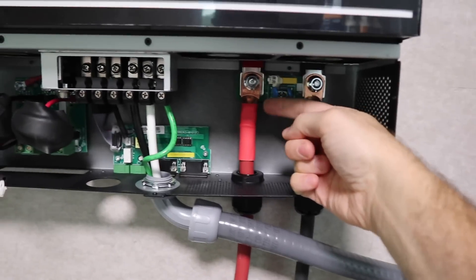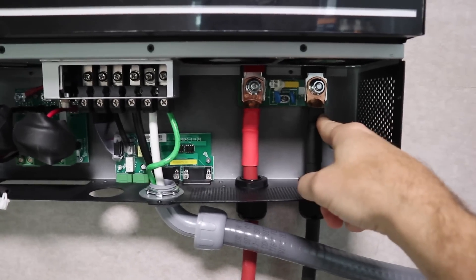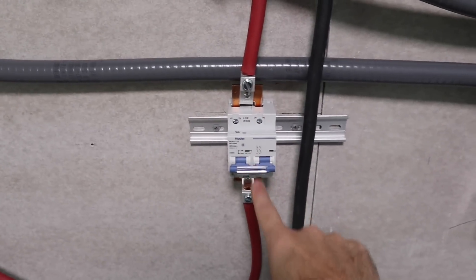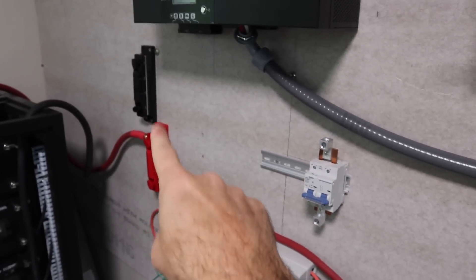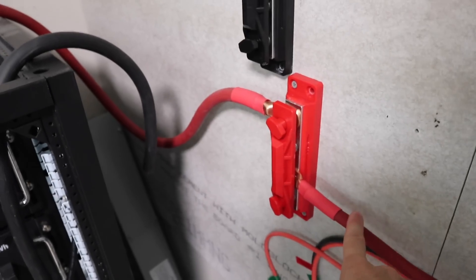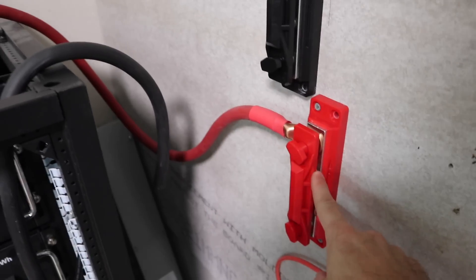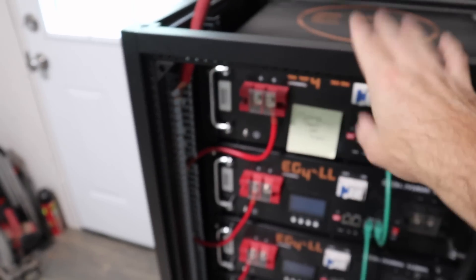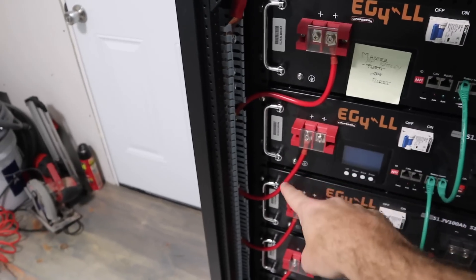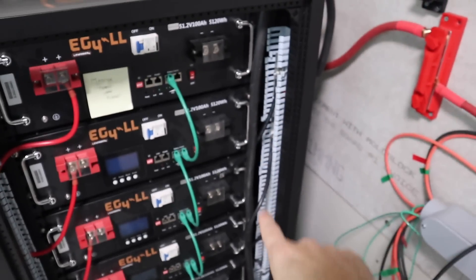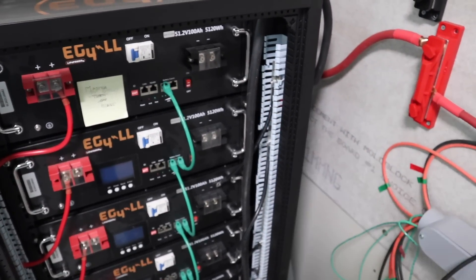Over here, we have our battery cables all set. We've got positive to positive, negative to negative. Positive comes down through our breaker and negative will go back to our negative bus bar. We've got our positive over to our positive bus bar and that's the two aught cable. The other two aught will come from this inverter over to this bus bar. Then this is four aught cable over to the bus bar on our battery cabinet. All of our batteries are connected to that bus bar. Obviously we'll be doing the same with the negative side.